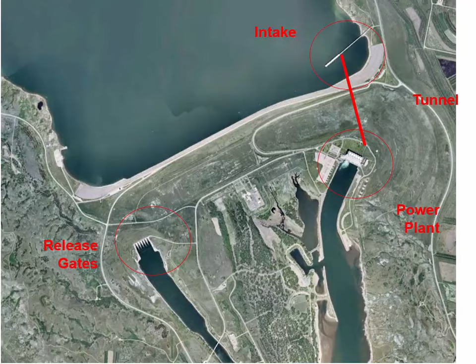I said 98% of the time they can put the water through the power plant, and it's just rarely and occasionally that they have any reason to open up the overflow spillway. This is one of those cases. Back in 2011, it rained a lot in the watershed upstream of the dam, and so it rained so much that they sent the maximum through the power plant, which is 50,000 CFS. And in the United States, flow rates are often measured in terms of cubic feet per second, and that's what this CFS means. So they were sending 50,000 CFS through the power plant, and here's how wet it was. They sent 110,000 through the overflow spillway.